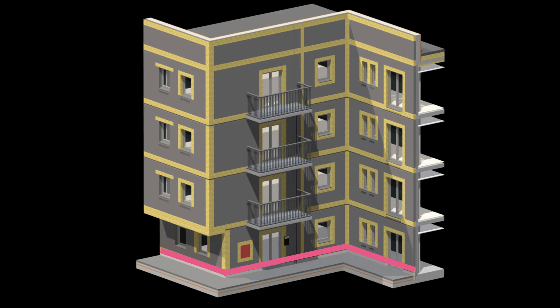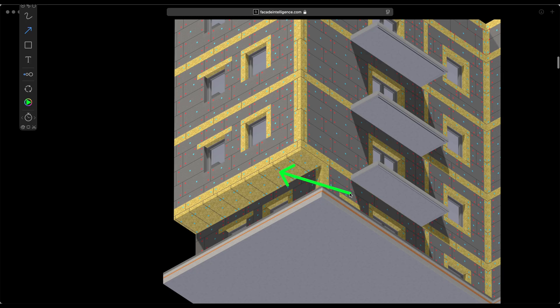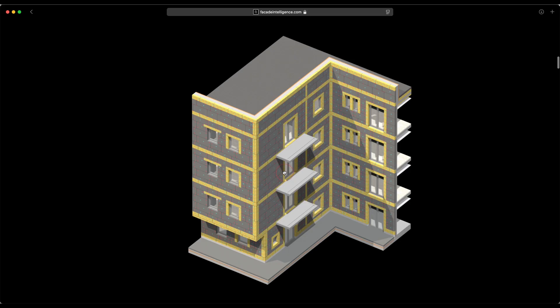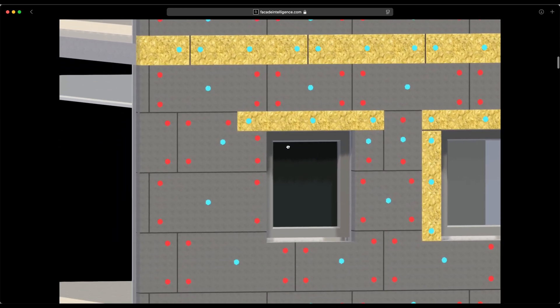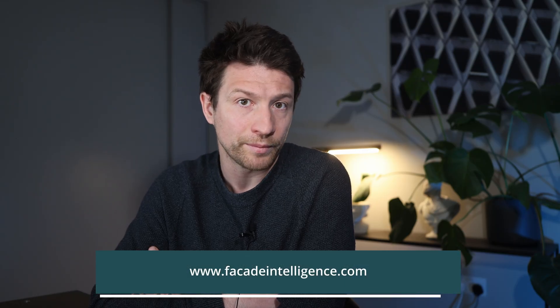The bulletin and case study are available to IST members and the general public for free. If you are in the architecture and construction industry, you should consider joining our community and supporting our cause. The key takeaways are: if a large-scale fire test has not been carried out for the EPS render system, fire barriers should be installed at floor slabs, party wall locations, and around openings. All horizontal surfaces such as balconies or protruding soffits should be insulated with mineral wool — EPS insulation should not be used in these locations. The use of fire barriers at lintels above windows only could be appropriate but is subject to large-scale fire test results. The bulletin also provides guidance on locations and quantities of fixings for both EPS insulation and fire barriers. Beyond fire safety, the case study includes best practice details for interfaces and window positions, backed up by thermal and condensation risk reports. Both the bulletin and case study are currently at draft stage and will be updated following feedback.